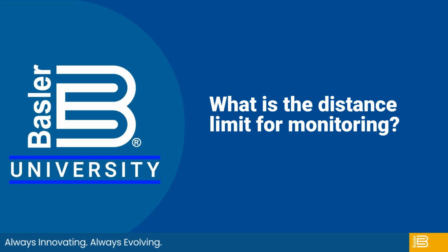What is the distance limit for monitoring, or does the control panel connect to the internet? Can it be monitored from anywhere? So I think the simplest answer there is standard Ethernet communications is about 300 meters. I have done ones that are longer than that. And basically, as long as you put an unmanaged Ethernet switch every 300 meters, it will continue. So it's no different than in a building.